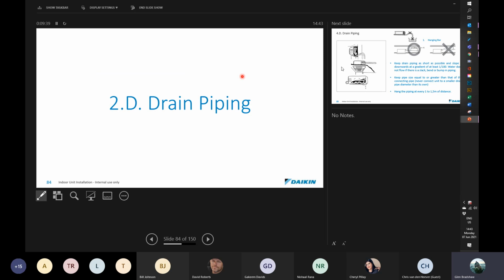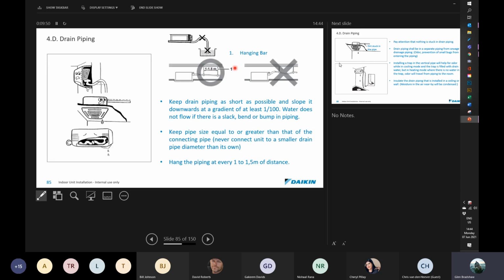Okay. Next one we're going to look at is obviously very often the very first call out that you get back to the system the day after it's been installed, and that is the condensate drains leaking. All right. Again, here are some images basically showing you we don't want to see the drain pipe going uphill first. Water does not flow uphill unassisted. Okay, so we don't want any U-bends up there, especially when there's no pump in the system, and mid walls do not have that unless you're installing one. But try and get away from that if you can.